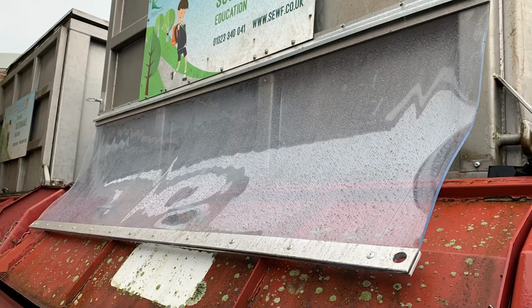The solution, after we'd had discussions with the operators, management and local engineers, was an expenditure of around about £1,200, putting in a weatherproof flap on the end to stop water seeping in there. And as a result of that, there will be less downtime during wet weather. But overall, what we've identified is 2 things. One, when you have a good operator who's well trained and knowledgeable, it makes a huge difference in how long that boiler operates for and how efficient it is. "Love your boiler," the operator said to us the first time we met with him, and that was very clear. And as a result of his enthusiasm, we have actually used him as a mentor for some of the other operators. And the second thing is, detail really matters.